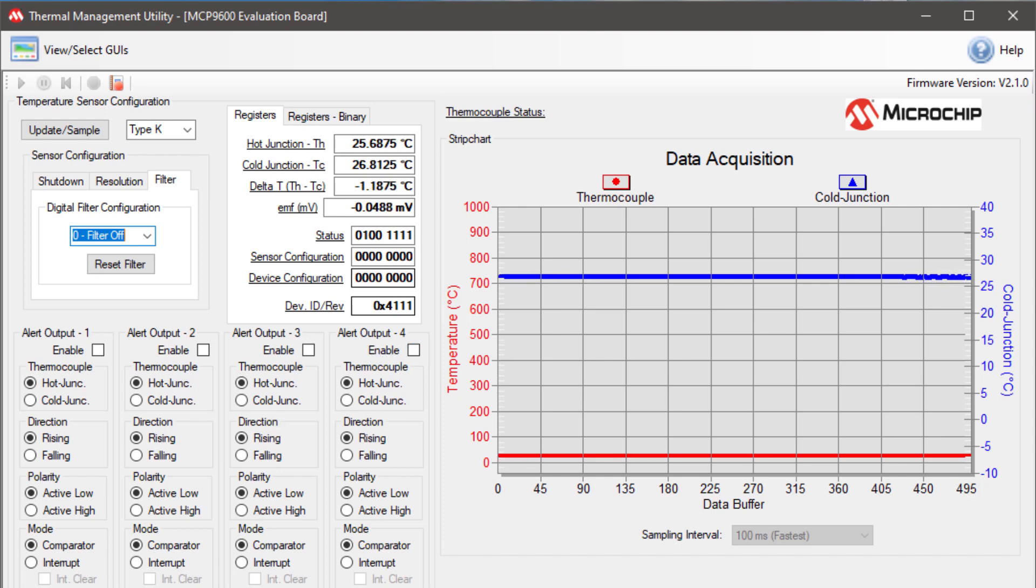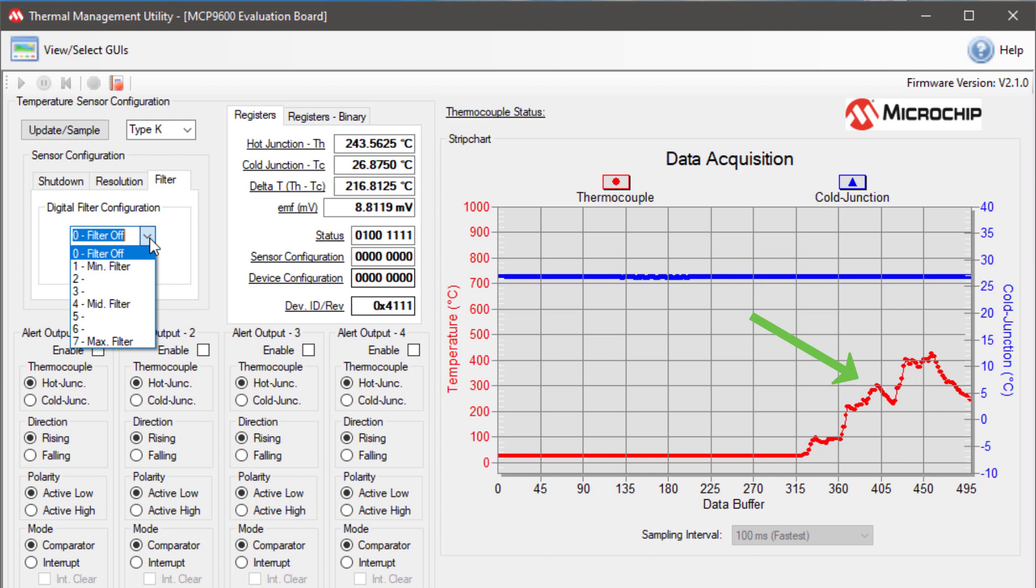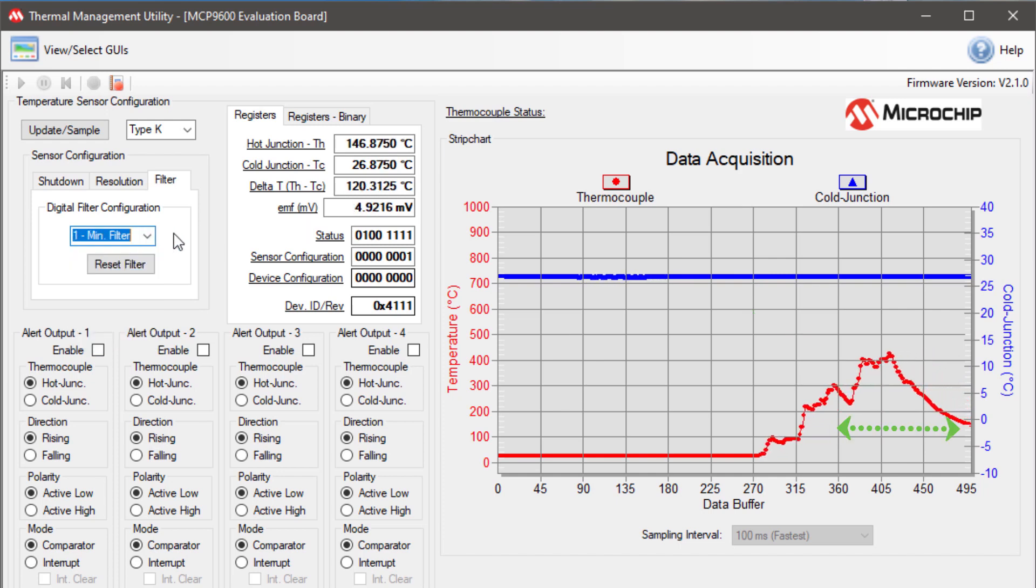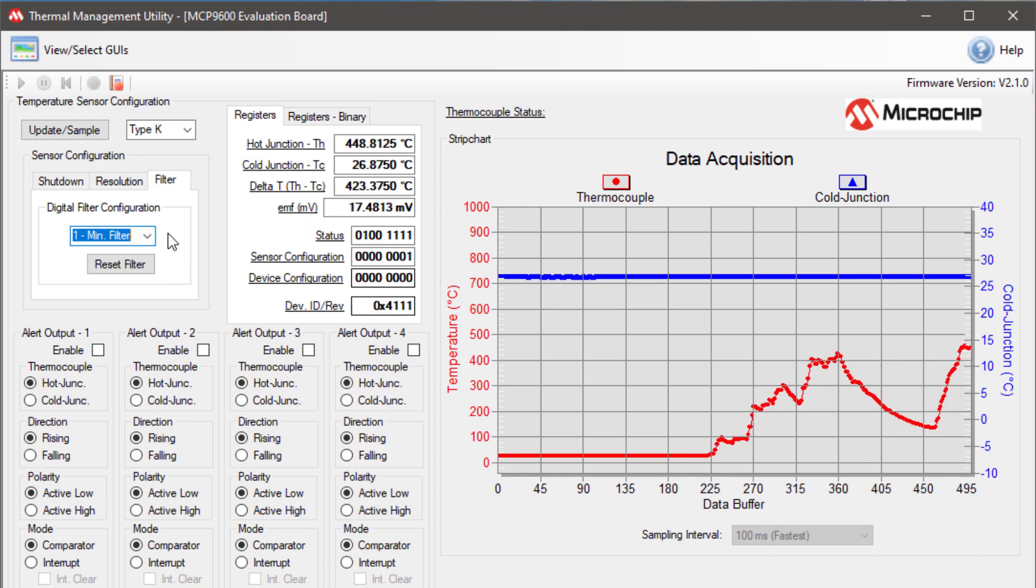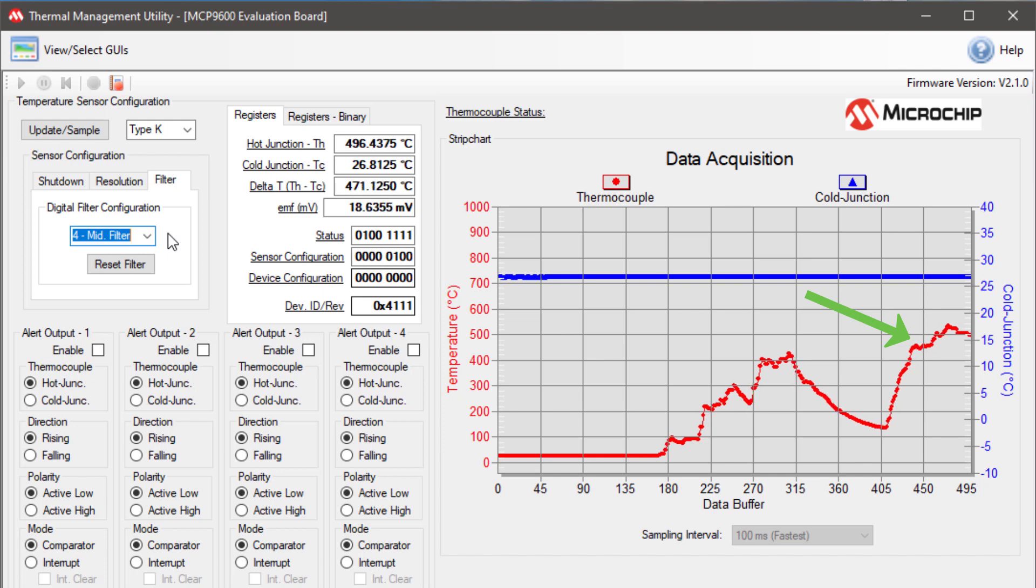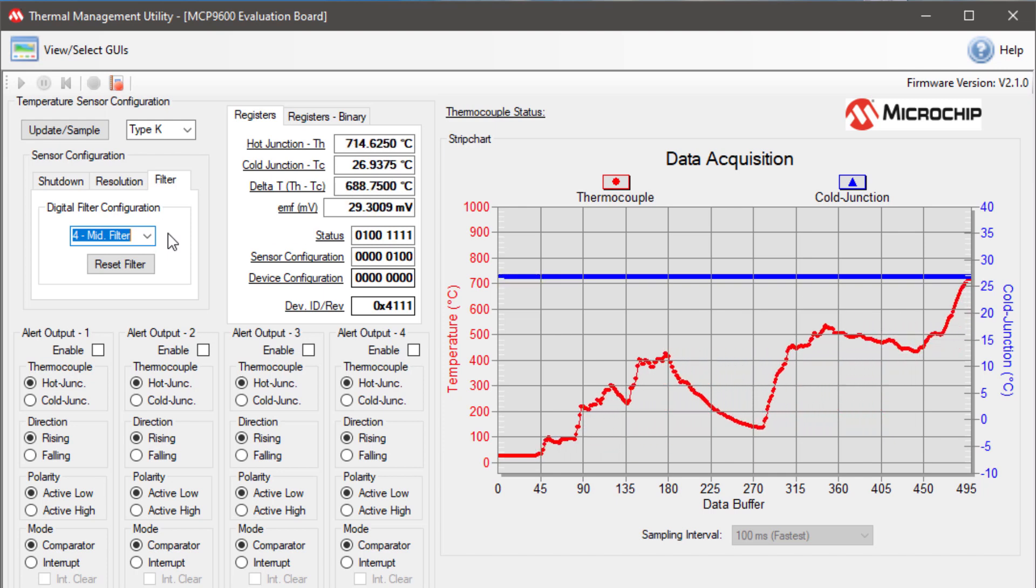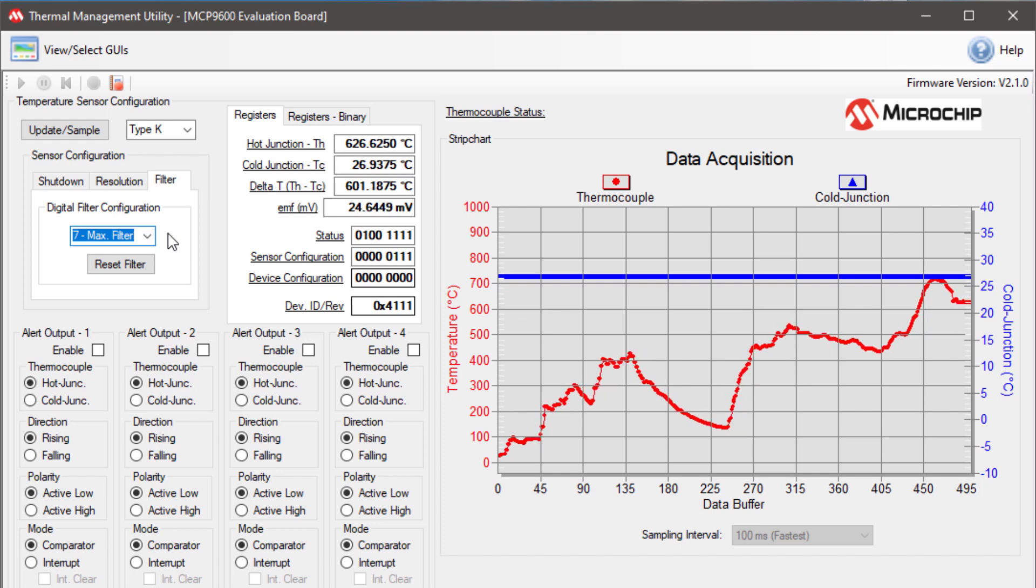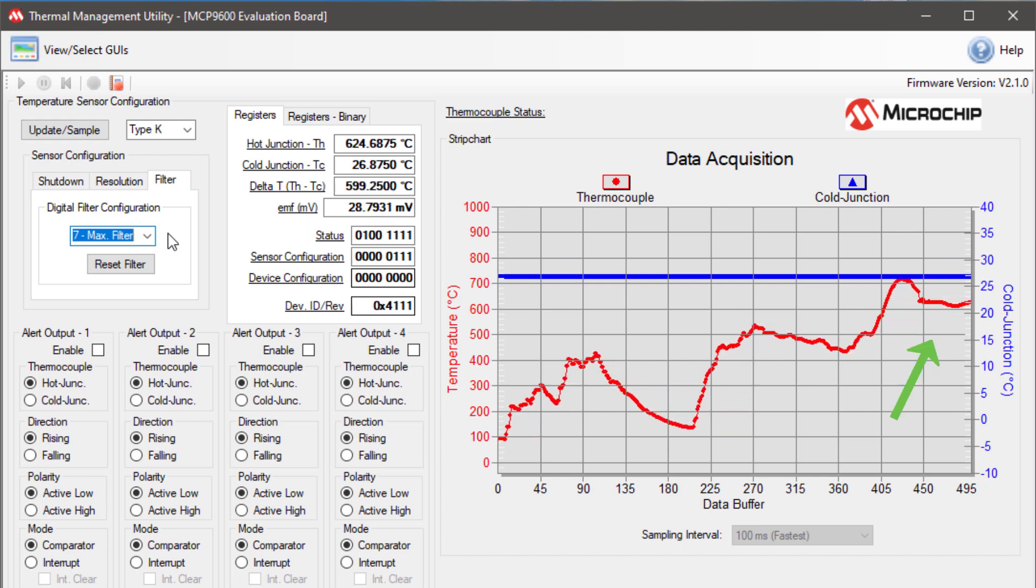Now, I'm going to add some heat to the thermocouple. We can see when the filter is off, the temperature sample is very bouncy. Then, at level 1, we cannot see the difference on the graph, but we can see it on the registers. Then, when the filter is at mid-level, you can see that the bouncing somewhat quiets down. And finally, when we set it to the maximum filter, which is 7, you can see that the temperature reading is nice and smooth and still tracks the temperature changes.